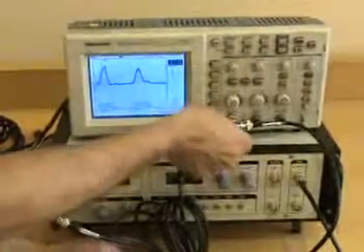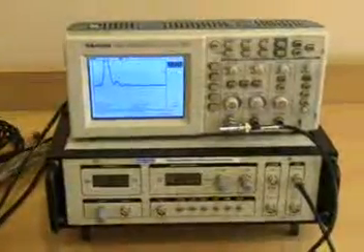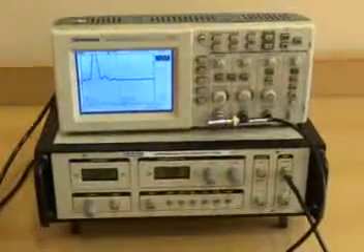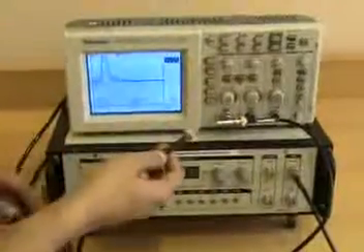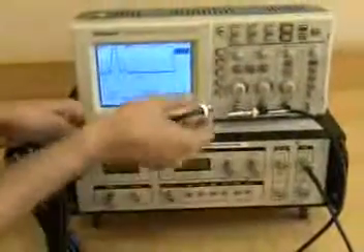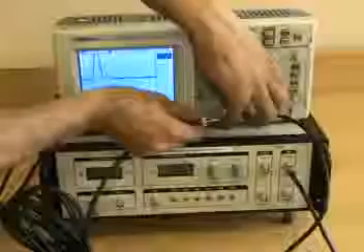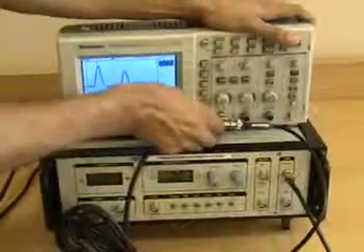Similarly, we can perform the experiment for different cables. Now as you can see, we are using the short range because the short range has got a fast pulse, so it is used for smaller cables, whereas this long TDR range is used for long cables in the range of say 50 meters or 100 meters.